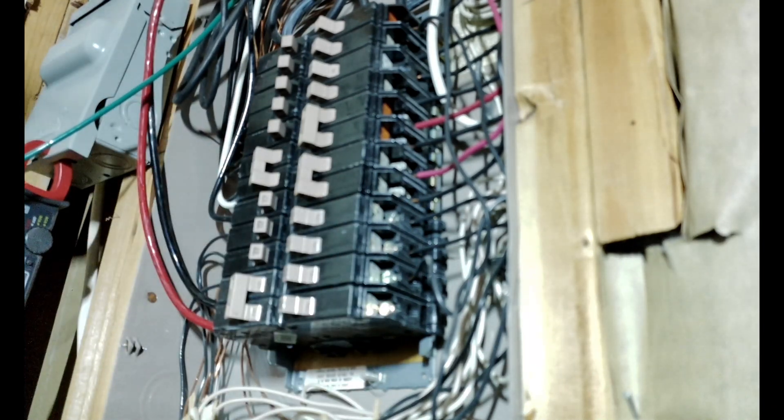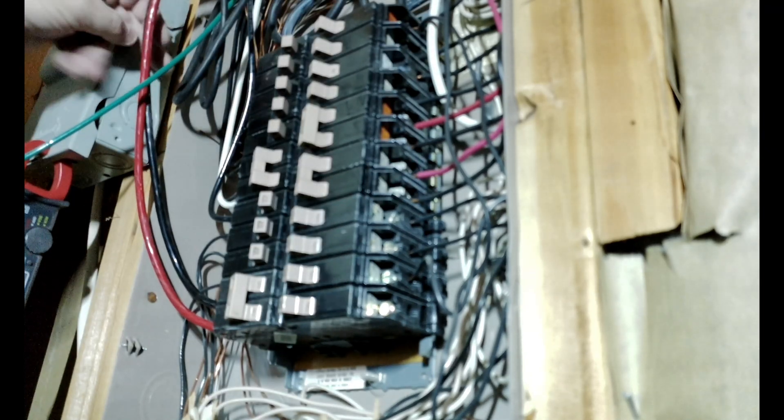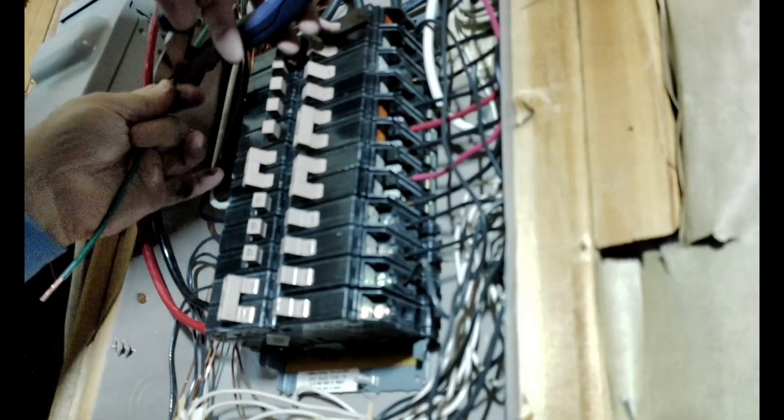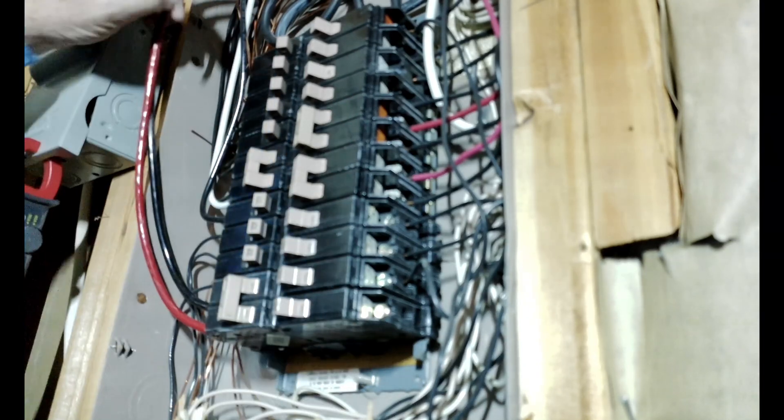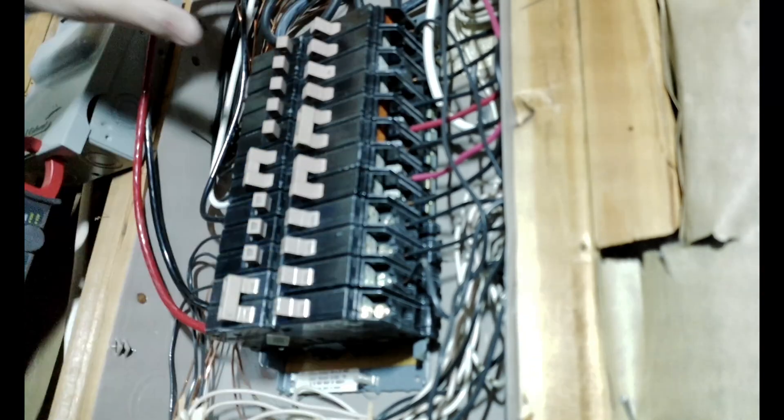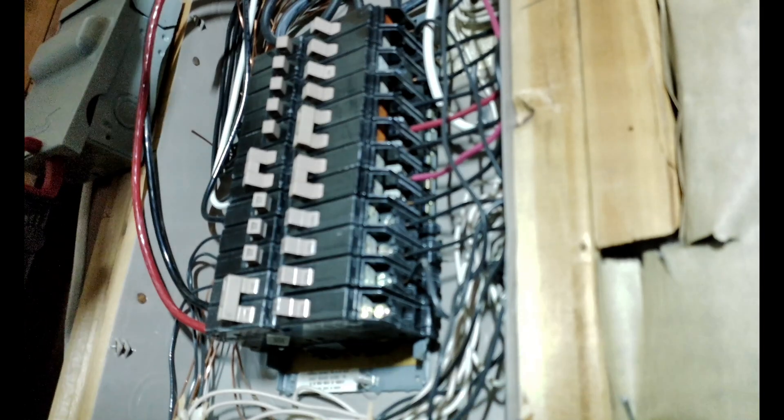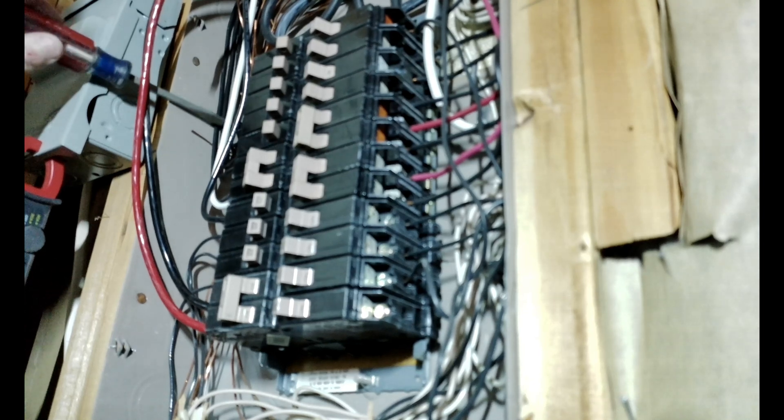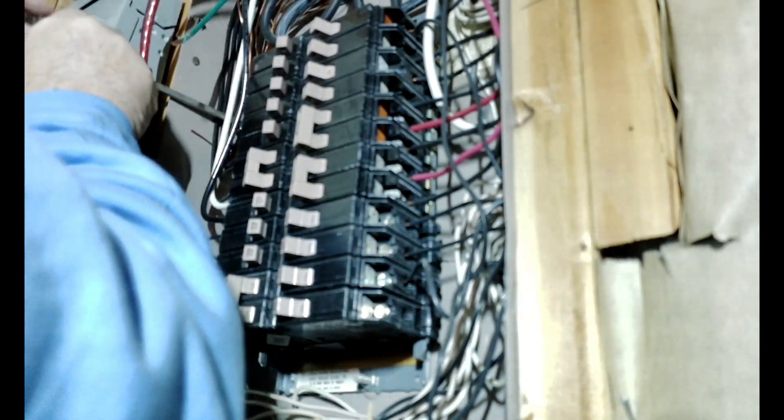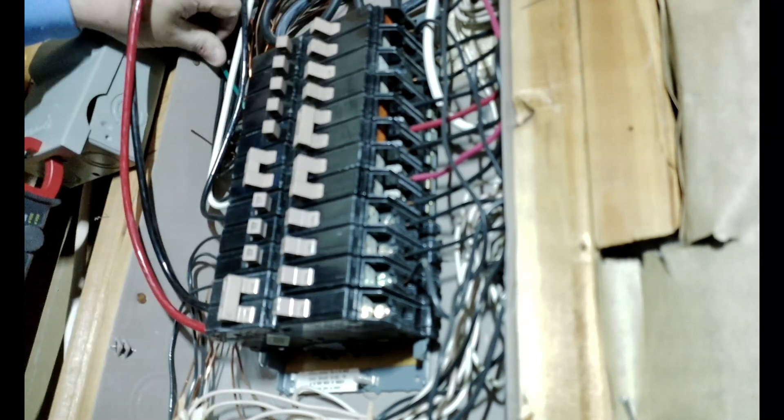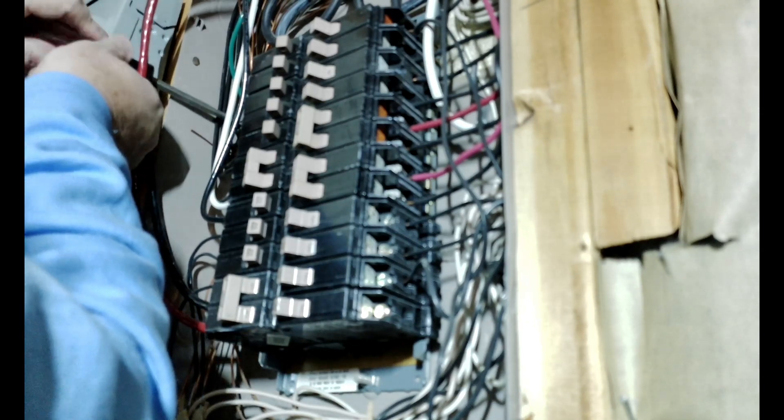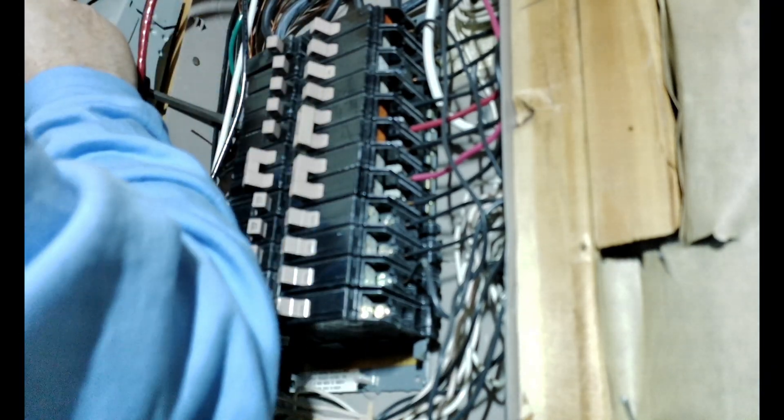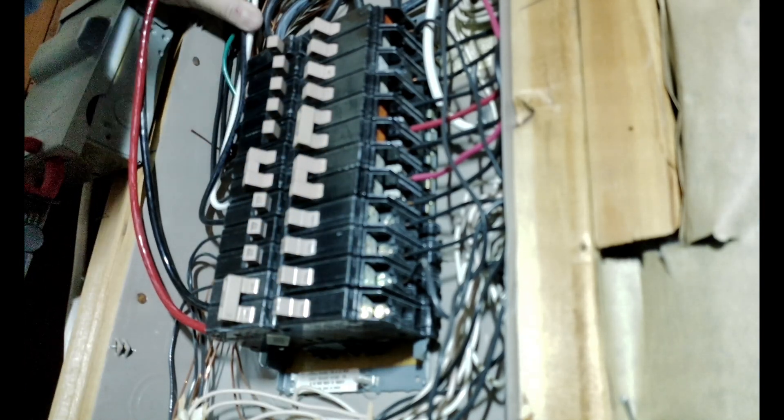That's really weird—they've got a single ground connection there. They don't have a bar at all like they do out in the garage. Still don't doubt what the heck these people were thinking when they wired this box. Just unbelievable, scary being scary. The modern boxes have multiple grounds you can connect to. This one seems to only have one giant one, which is very strange. Okay, so we've got that circuit wired. We've got this one cleaned up.